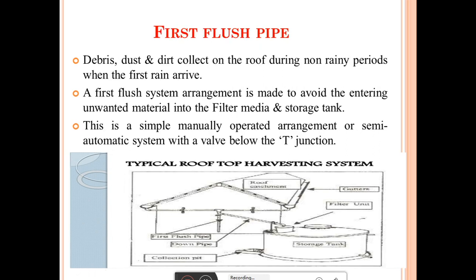The next component is the first flush pipe. During the first rain, debris, dust, and dirt collected on the roof during the non-rainy period are washed off. A first flush system arrangement is made to avoid unwanted material entering the filter media and storage tank, which would otherwise disturb filtration efficiency. This is a simple manually operated or semi-automatic system with a valve below the T-junction. The first rain is allowed to pass through the first flush pipe and is not stored in the storage tank.